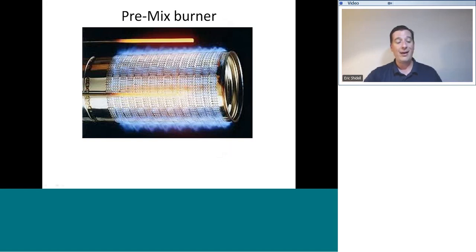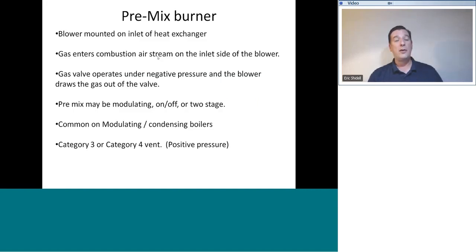So to review on the premix burner, a blower is mounted again on the inlet of the heat exchanger. Gas will enter the combustion airstream on the inlet side of the blower. So yeah, that squirrel cage, that rotating blower, has gas and air being mixed right in the fan. That's kind of neat, kind of crazy when you think about it. The gas valve operates under negative pressure, and the blower draws the gas right out of the valve.